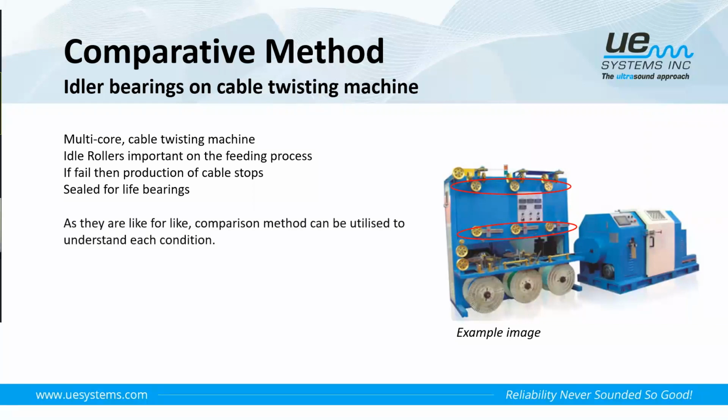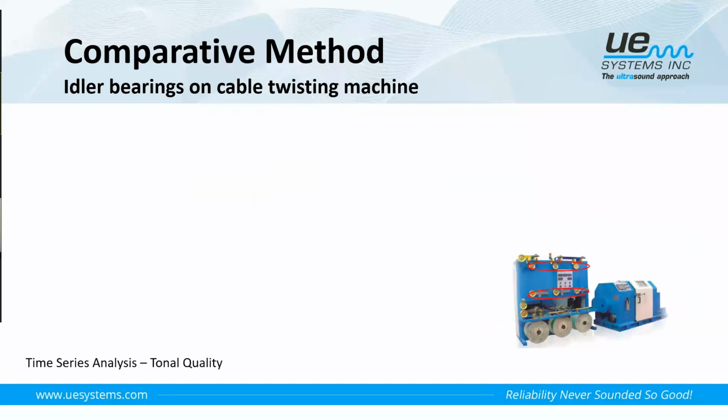As they are like for like, under the same speed and load all the time, we can utilize the comparison method at the first point of inspection to see which ones are in what condition and what work might need to be done. So on this particular cable twisting machine, there were 5 idler bearings. So we can take sound recordings of each of these bearings, record it, and then compare them and see what they are like to where they are in their health.